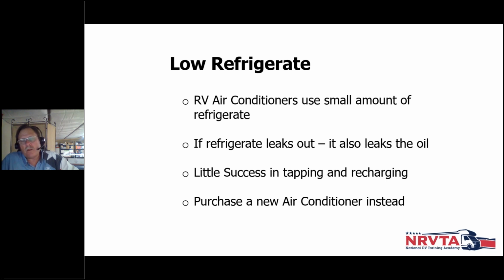You put refrigerant back in there, but because there's no oil pan for this air conditioner, this oil travels through with the refrigerant. It travels through the compressor, through the coils, comes back to the compressor, and does its job all over again. If that refrigerant leaks out, it takes its oil with it. When that happens, you may have problems later because there's no refrigerant in there. And if you've lost the oil, now you've got a compressor running without any oil. We know what happens to metal against metal grinding of these cylinders and pistons.